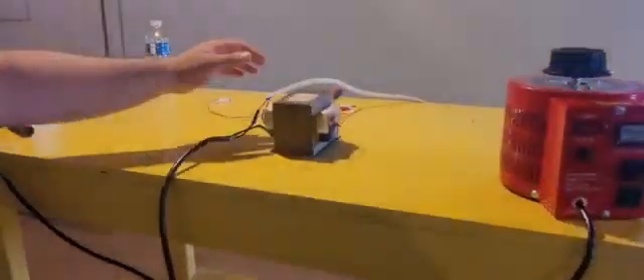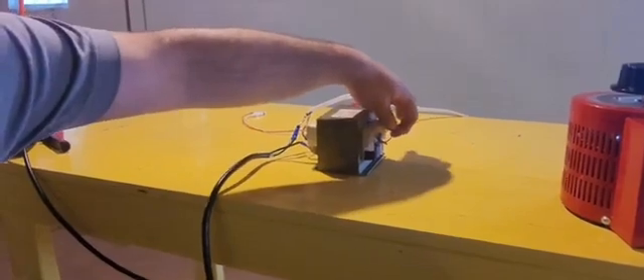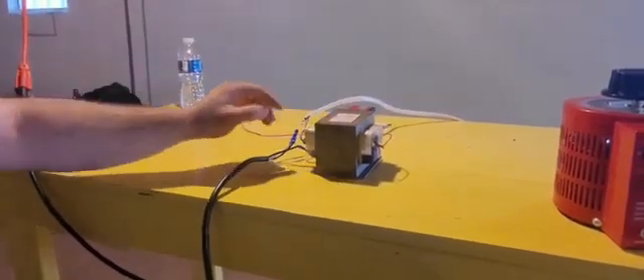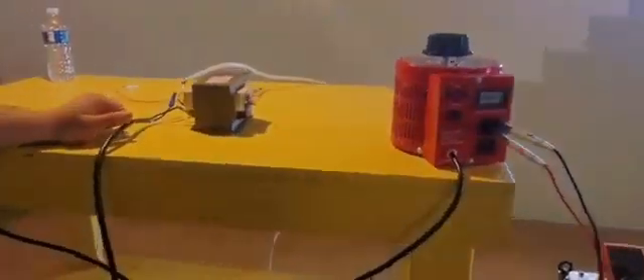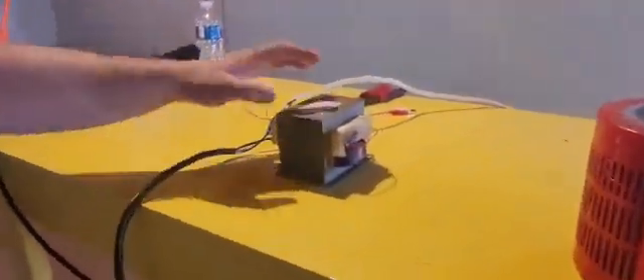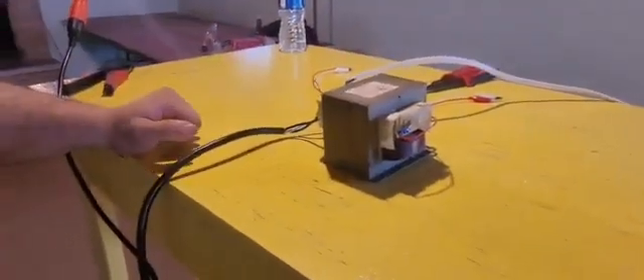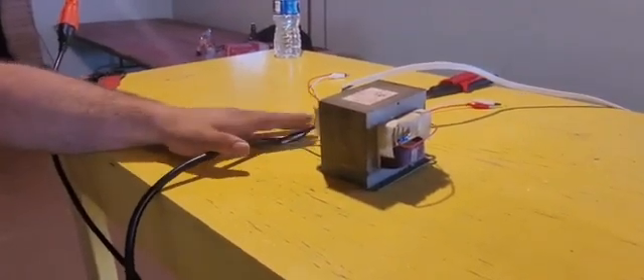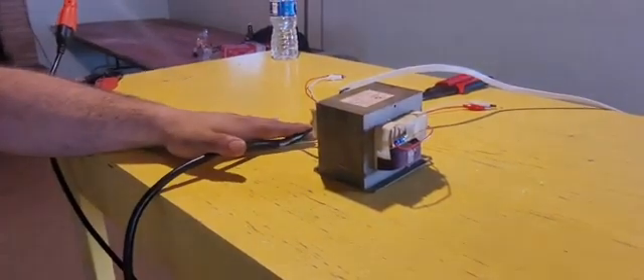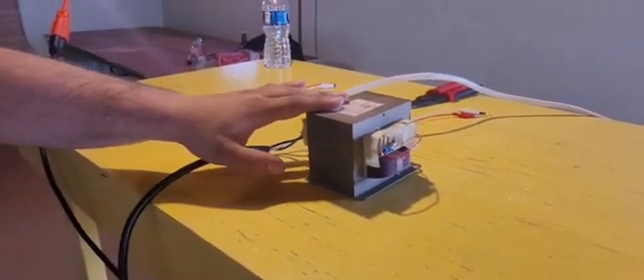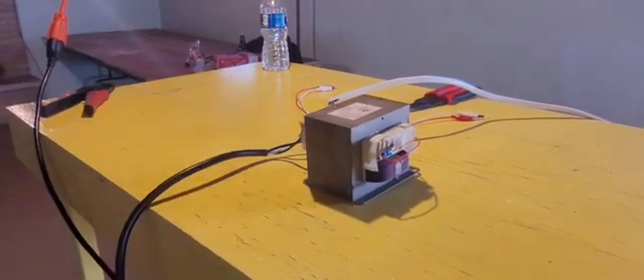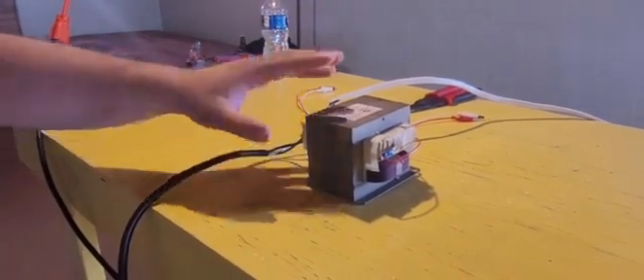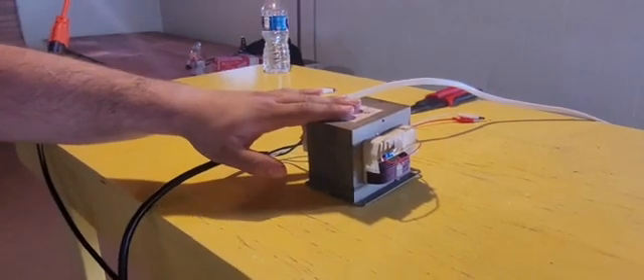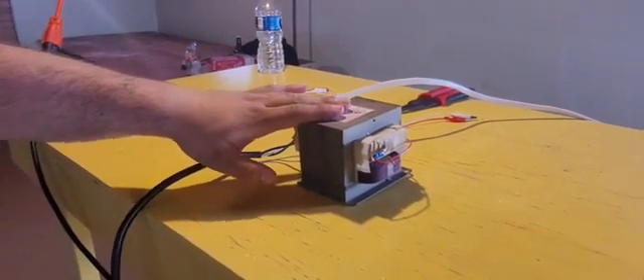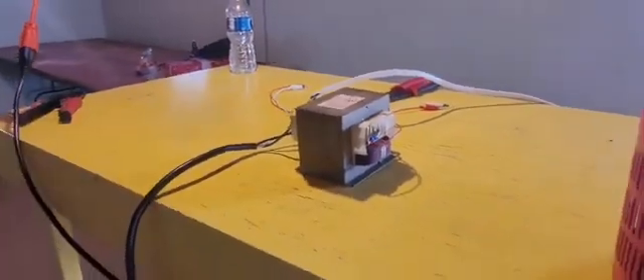And this is a microwave oven transformer with the secondary shorted, the high voltage shorted to the case, and it is hooked in series with the generator. We do this to limit current. This setup is called an inductive ballast. As the current through the wires to the generator rises, more voltage will drop across the ballast, again, the microwave oven transformer. This will limit the current going to the X-ray generator.